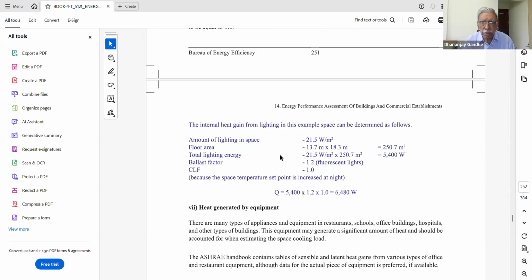to calculate the heat gain from lighting. It works out like this: the area of the building is given here. Floor area is 13.7 by 18.3. That's the floor area. Then the lighting density is 21.5 watts per m square. This is specified. So the area is 13.7 by 18.3, so 250. So the total lighting energy is area multiplied by the watt density, LPD, lighting power density. So this is 250 by 21.5, which is equal to 5,400 watt.